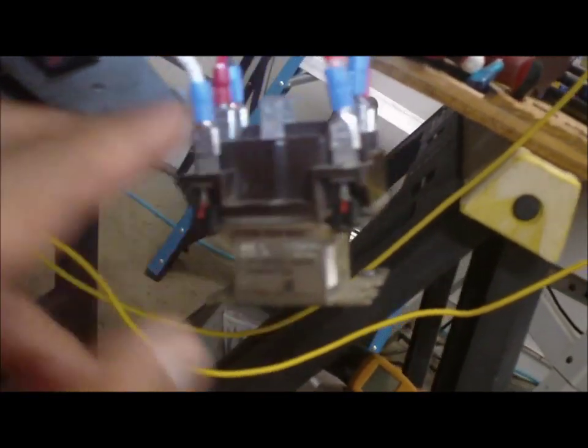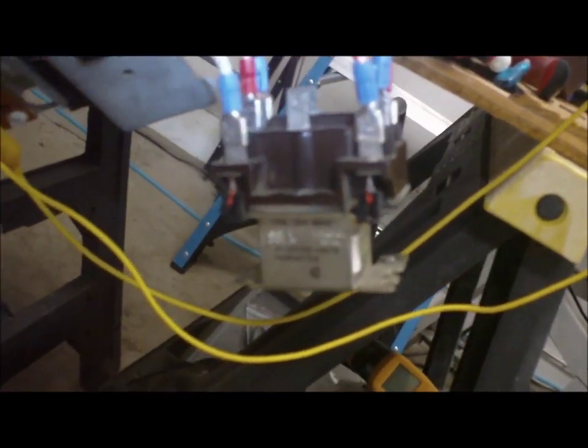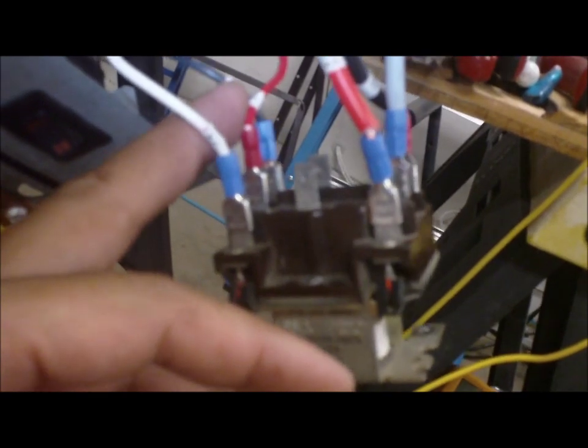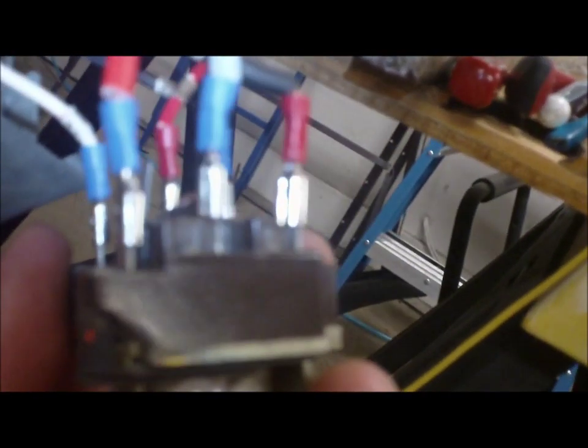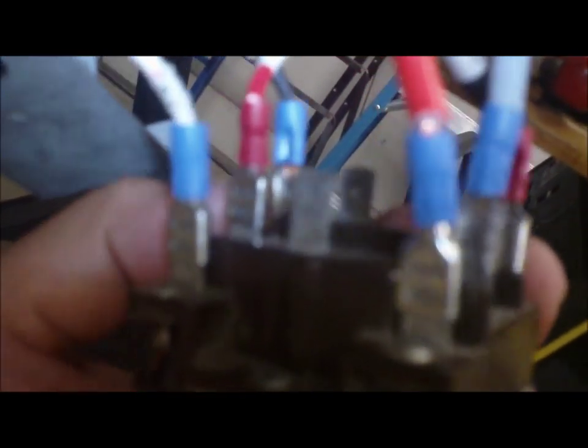Like I said, this 24-volt coil right here goes to your limit switch and common 24 volts, and this goes to your red from your transformer right here, and this one goes to your pressure switch. And behind here are your 120 volts. This goes from your primary from your transformer, and this one goes to your inducer draft motor.